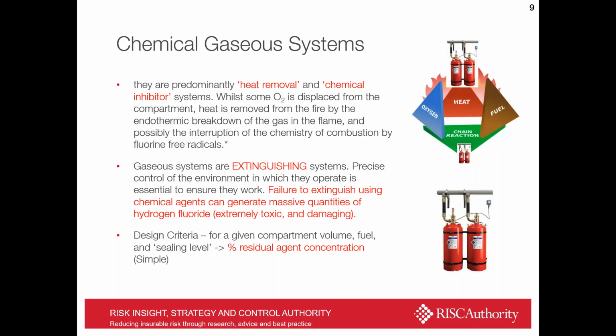Many are becoming slightly less desirable due to the greenhouse gas contribution that they can make. But these, again, are extinguishing systems. They need to extinguish the fire in order to fulfill their remit. And with these systems, because generally they are fluorinated compounds, if you don't extinguish the fire with these types of chemicals, it can lead to massive production of hydrogen fluoride, which is a very toxic and damaging gas, something which is highly undesirable. But the design criteria, again, is very simple.